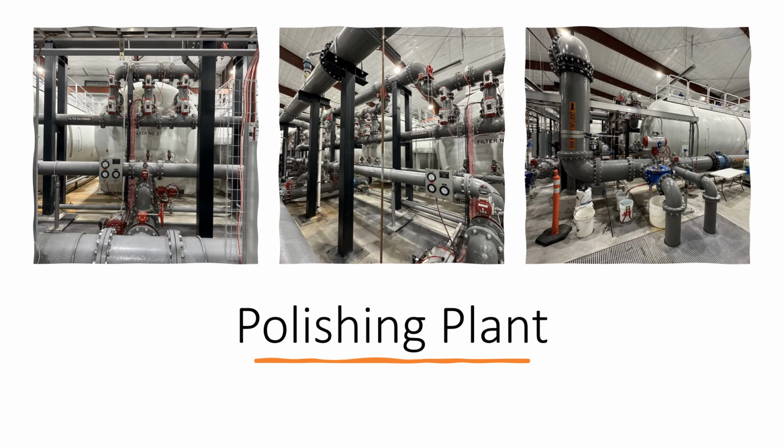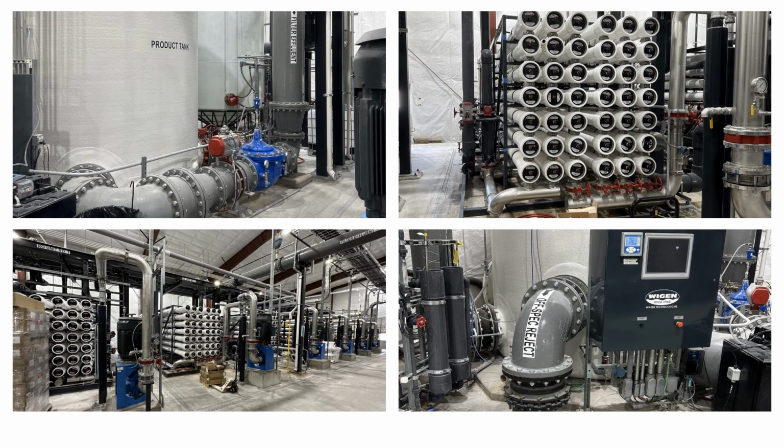The picture on the right shows the raw influent water comes in at about 11.1, 11.2 pH from the tailings dam, and that water is run through multimedia filters. Those are those big white filters that you can see. They have 6 of them, and then we use CO2 injection to drop the pH down to around 7.5, 7.4. And depending on the quality of the water going through there, if there's any salt in it, we also have the ability to run it through RO, reverse osmosis filters.